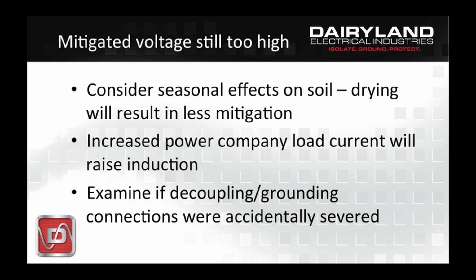Finally, one possibility that should at least be considered is if the decoupler or some type of grounding system that attaches it were severed, that would affect the mitigation system. If a point that had been mitigated is now open-circuited, then the pipeline will rise to the open circuit voltage, basically the unmitigated voltage.